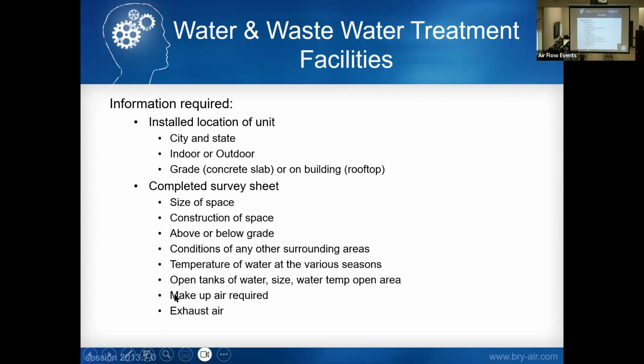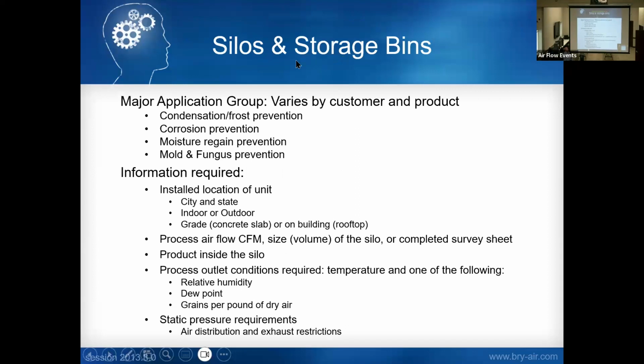Again, same kind of temperature, same kind of data, but here we need to know the temperature of the water at various seasons. And again, open tanks are critical in water treatment. Silos. When you're doing a wastewater plant like that, is there a balance between pulling moisture off of the surface and, how do you balance that? Because I imagine you bring that dew point down, depending on the temperature. So we bring the dew point down, I think it's 5 degrees below that pipe sensor. As the water changes and the outside air changes, that setting is constantly changing. As that pipe temperature changes, our dew point set point changes automatically.